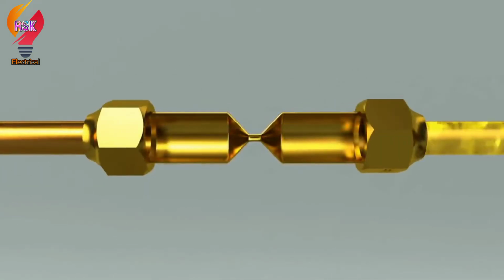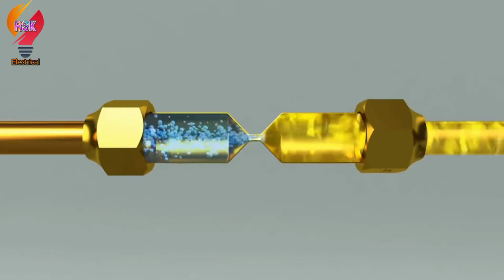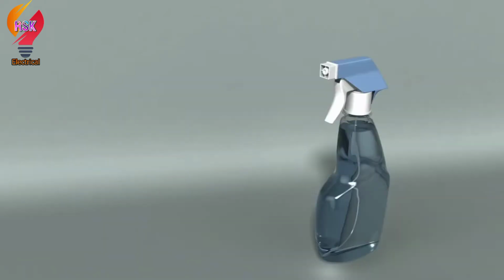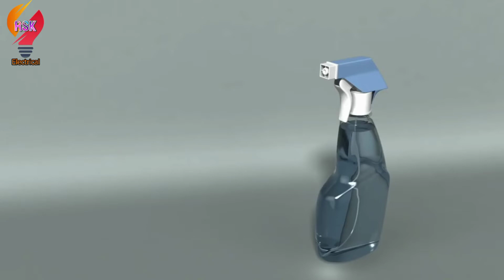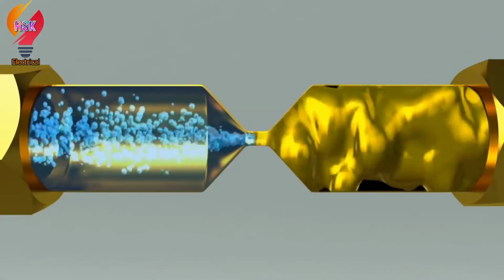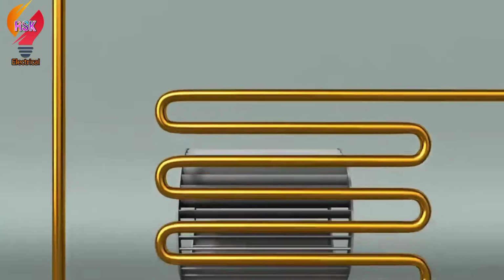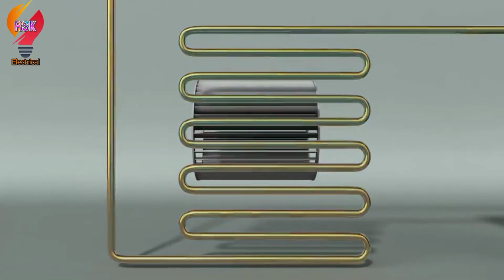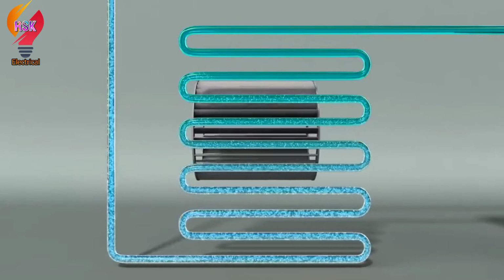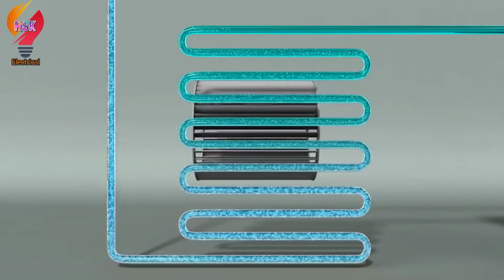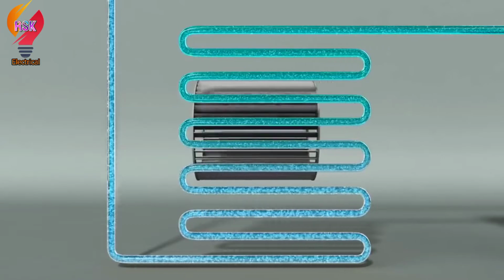The refrigerant passed through a condenser becomes liquid and flows into the expansion valve. There is a section in the expansion valve where the piping gets narrow, and as the refrigerant passes here, it splits up into many pieces. What we see here is similar to the principle behind water being spread from a spray. As the pressure on the refrigerant drops, its temperature drops dramatically as well. The refrigerant with lowered temperature then goes into an evaporator to steal away heat. An evaporator is literally a device that evaporates liquid into gas. Cooled refrigerant steals away the heat in the room and evaporates.